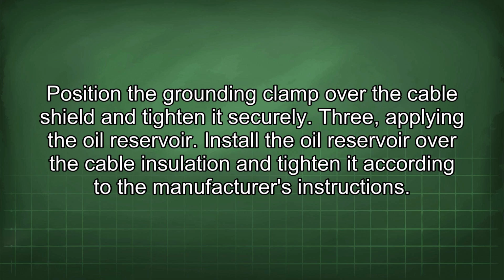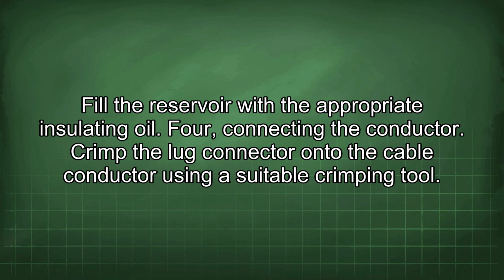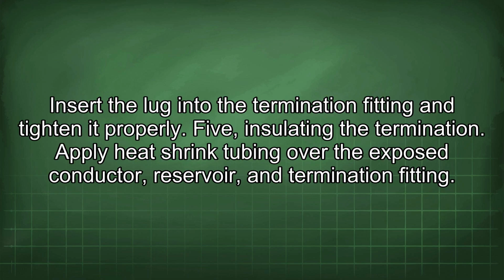3. Applying the oil reservoir. Install the oil reservoir over the cable insulation and tighten it according to the manufacturer's instructions. Fill the reservoir with the appropriate insulating oil. 4. Connecting the conductor. Crimp the lug connector onto the cable conductor using a suitable crimping tool. Insert the lug into the termination fitting and tighten it properly.